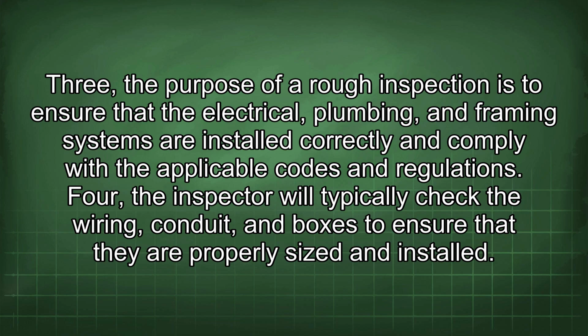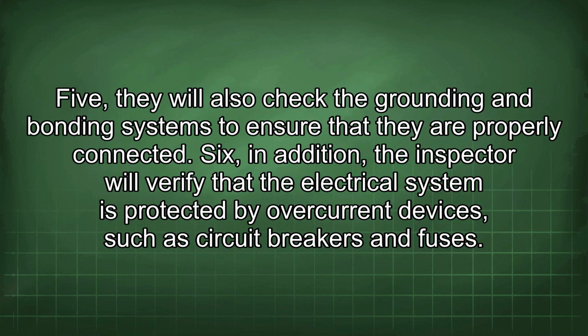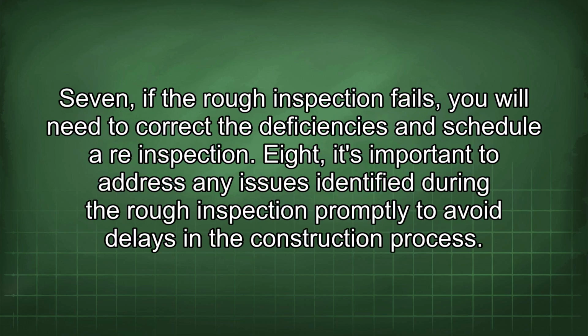4. The inspector will typically check the wiring, conduit, and boxes to ensure that they are properly sized and installed. 5. They will also check the grounding and bonding systems to ensure that they are properly connected. 6. In addition, the inspector will verify that the electrical system is protected by overcurrent devices, such as circuit breakers and fuses. 7. If the rough inspection fails, you will need to correct the deficiencies and schedule a re-inspection. 8. It's important to address any issues identified during the rough inspection promptly to avoid delays in the construction process.